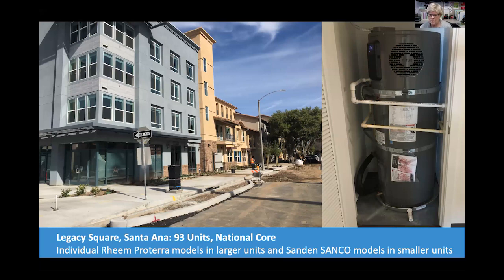But this issue of where the air that the heat pumps are extracting the heat from is coming from is an important issue. In California, heating isn't such a big deal, and they don't condition corridors. But in a corridor building in Boston, that corridor is conditioned because we are required to provide heat from September 15 to June 15. And so the heat pump is just stealing the heat from the conditioned air in the corridor to transfer it to the water.